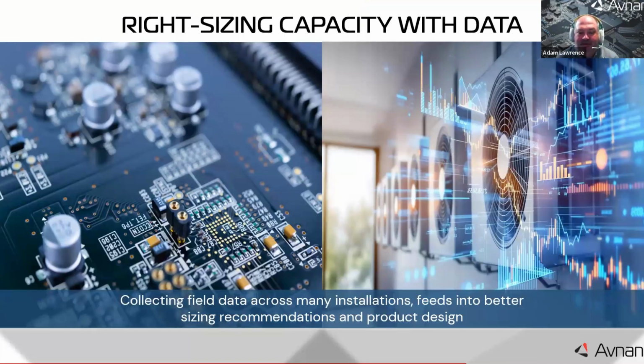Let's consider capacity first. We design a heat pump or AC with a certain BTU rating, but the actual demand can vary with weather, occupancy changes, building modifications, and so on. With embedded sensors and logging, the controller can measure how often and how hard the system is running to meet set point. If the compressor is at full output for extended periods and still not maintaining temperature on the hottest days, that's a clue that the unit is undersized for the load. Conversely, if it's short cycling frequently, it might be oversized.